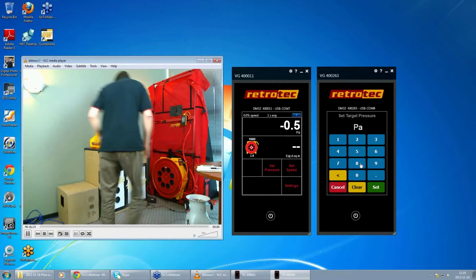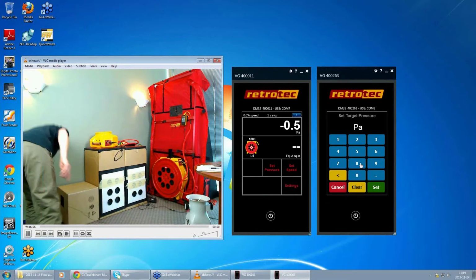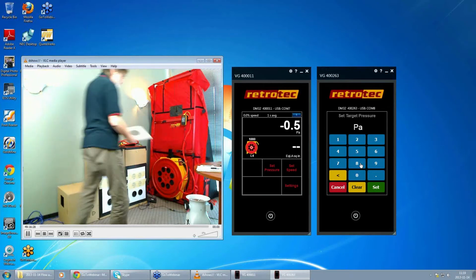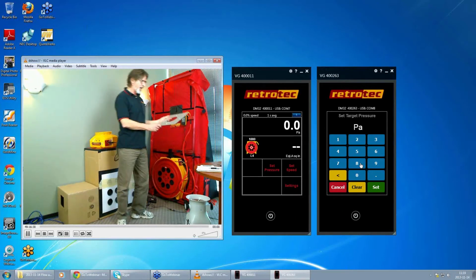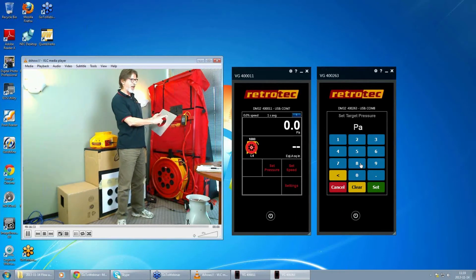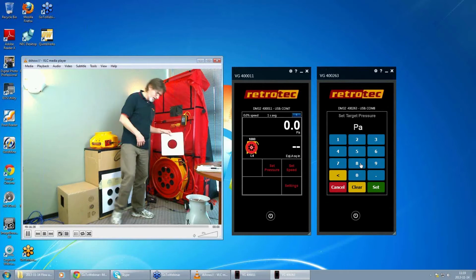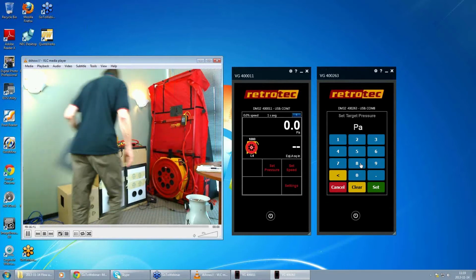We also have a procedure for checking duct testers, which uses this calibration plate, and the flow rate is marked right on the plate. This can go on the end of the flex duct, and it's a great way to check the calibration of your fan, or of your duct tester, I should say.